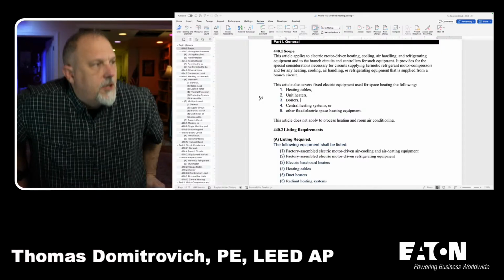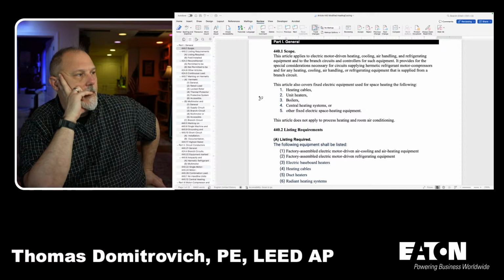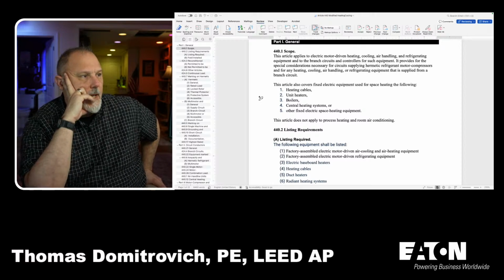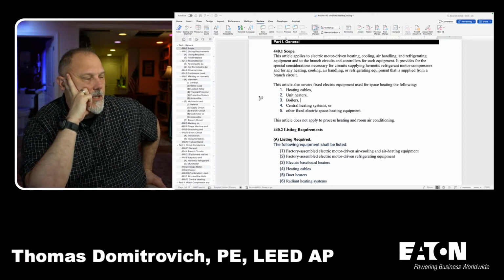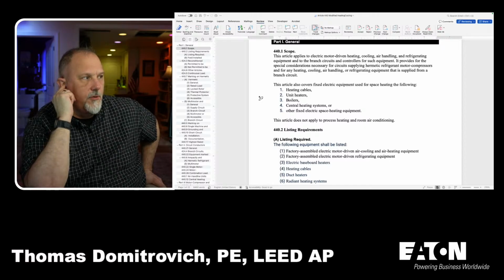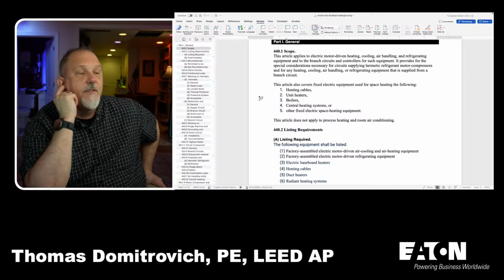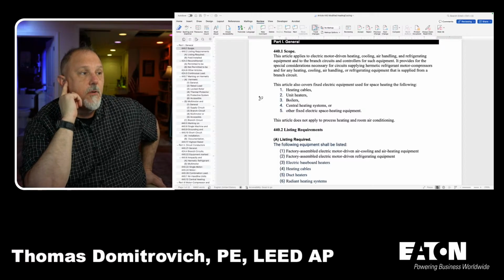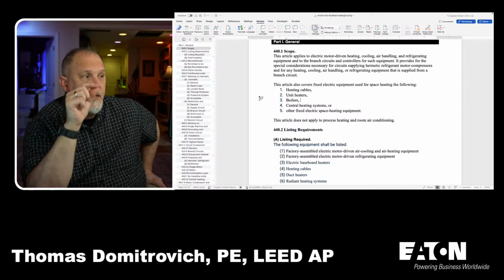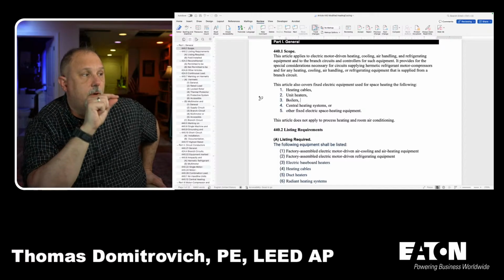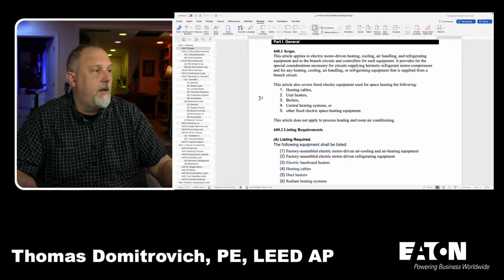This article applies to electric motor-driven heating, cooling, air handling, and refrigerating equipment, and to the branch circuits and controllers for such equipment. It provides for the special considerations necessary for circuits supplying hermetic refrigerant motor compressors and for any heating, cooling, air conditioning, air handling, or refrigerating equipment that is supplied from a branch circuit. This article also covers fixed electric equipment used for space heating, including the following.